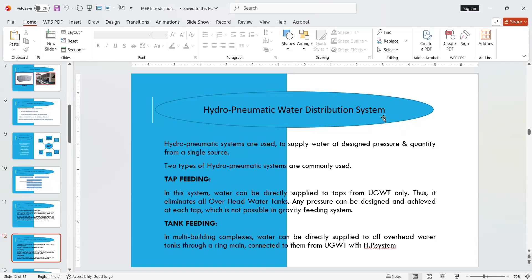In high-rise tower projects, usually hydropneumatic systems are divided into zones. For example, if your building is of 30 floors, we cannot maintain pressure with a single line, so we have to do it zone-wise. That means there will be two zones, low zone and high zone. For example, in a 30 floor building, we can say G plus 14 floors will be the low zone, and then 15 to 30 will be the high zone.